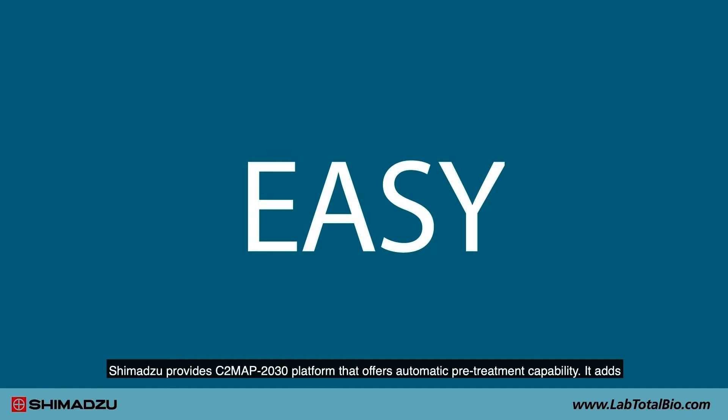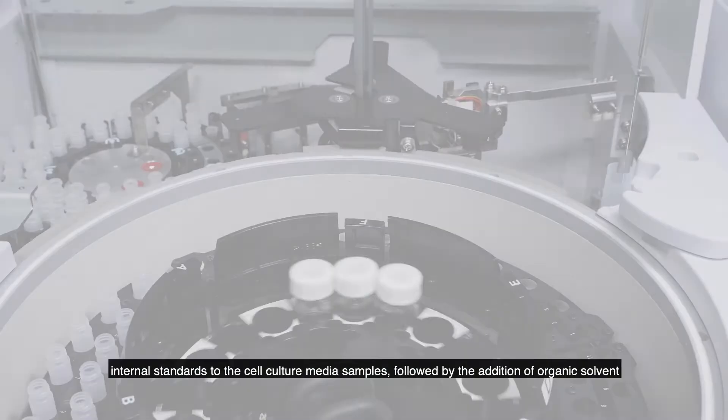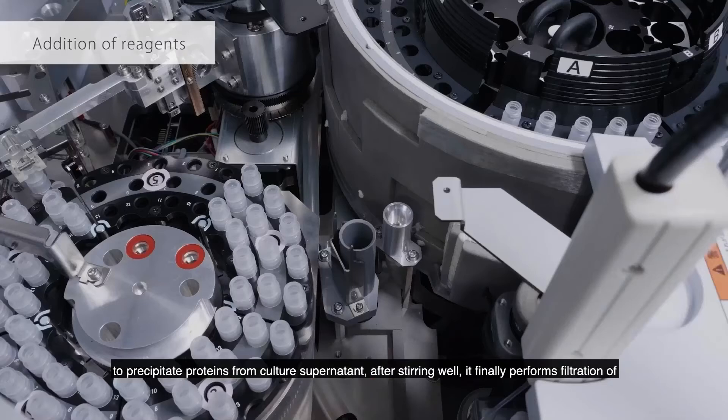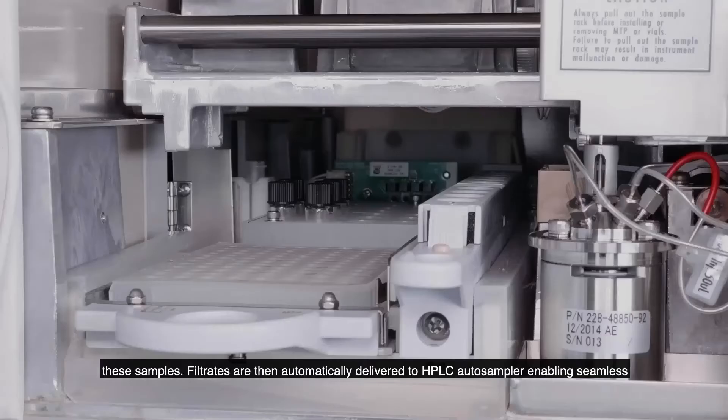Shimadzu provides the CLAM-2030 platform, which offers automatic sample pretreatment capability. It adds an internal standard to the culture media sample, followed by the addition of organic solvent to precipitate proteins from the culture supernatant. After mixing well, it performs filtration of the sample. Filtrates are then automatically delivered to the HPLC autosampler, enabling seamless LC-MS/MS measurement using the cell culture profiling method package.